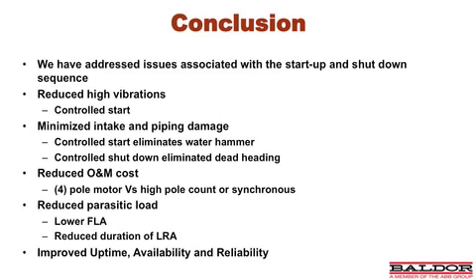So in conclusion, we have addressed issues associated with the startup and shutdown sequence. We've reduced high vibration using a control start methodology. We've minimized intake and piping damage, specifically with the control start, eliminating water hammer, as well as the shutdown, a control shutdown, eliminating deadheading conditions.